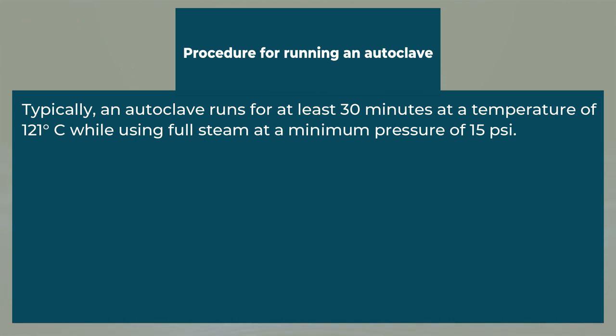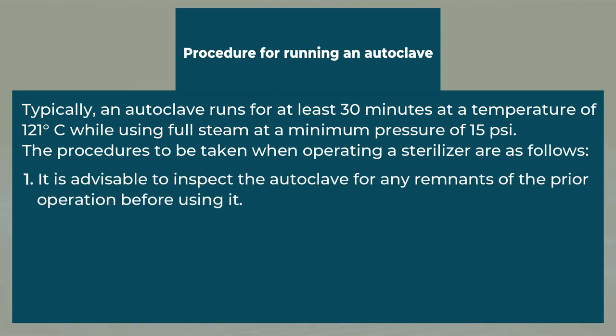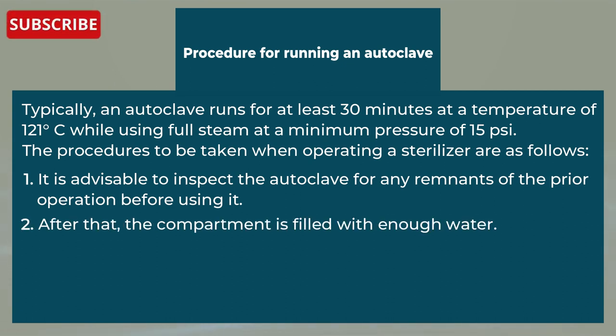Now let's see the procedure for running an autoclave. Typically, an autoclave runs for at least 30 minutes at a temperature of 121 degrees Celsius using full steam at a minimum pressure of 15 psi. The procedures are as follows: First, inspect the autoclave for any remnant of the prior operation before using it. Second, fill the compartment with enough water. Third, fill the container with the items to be disinfected. Fourth, close the cover and tighten the fasteners to ensure air tightness, then turn on the electric heater.